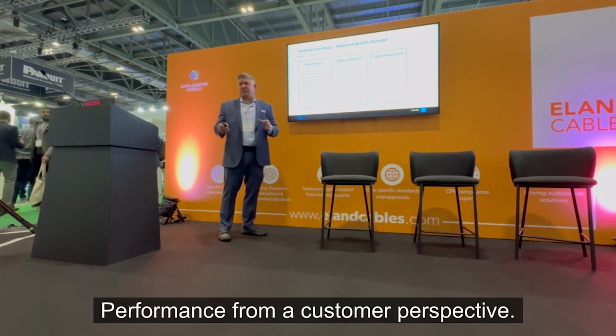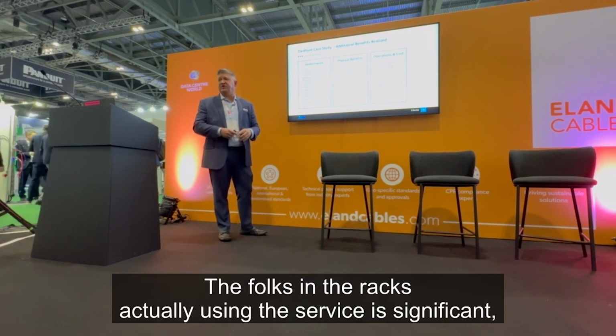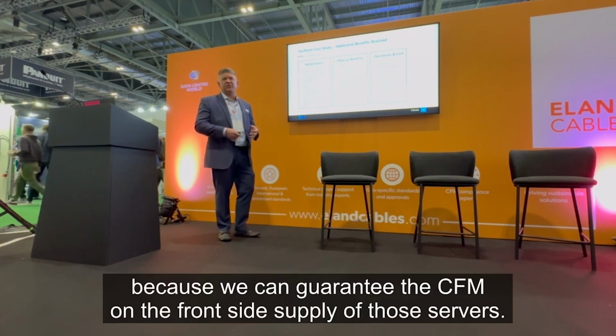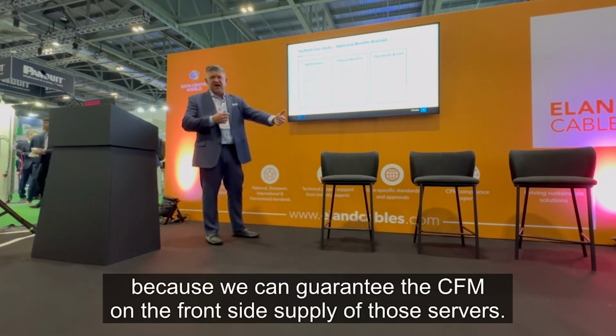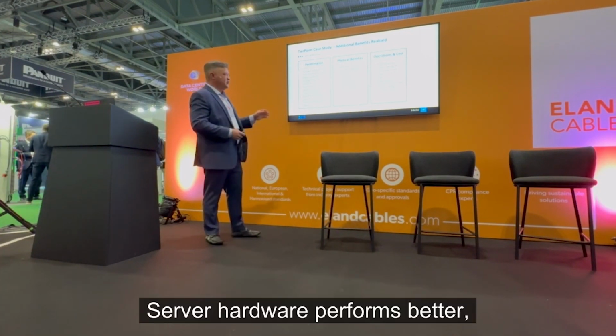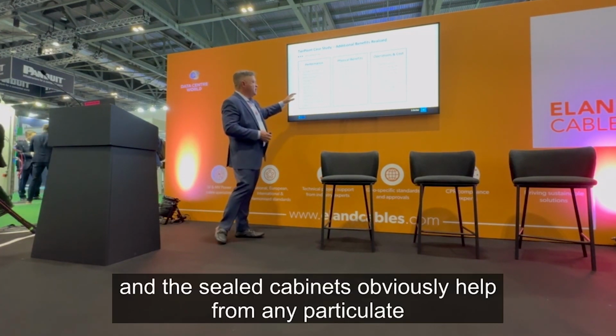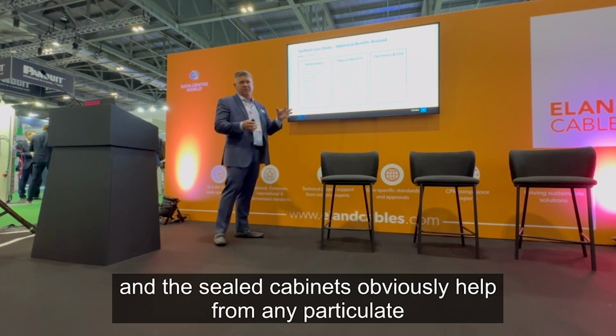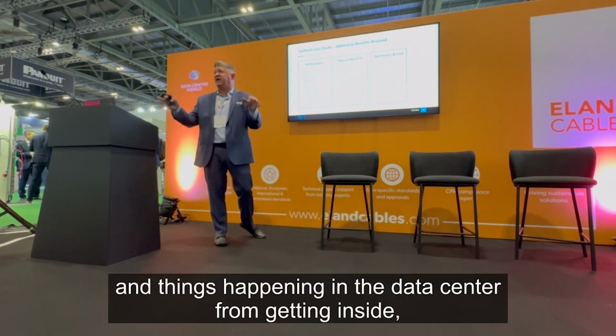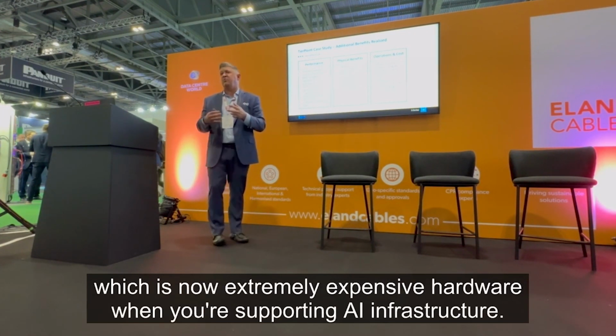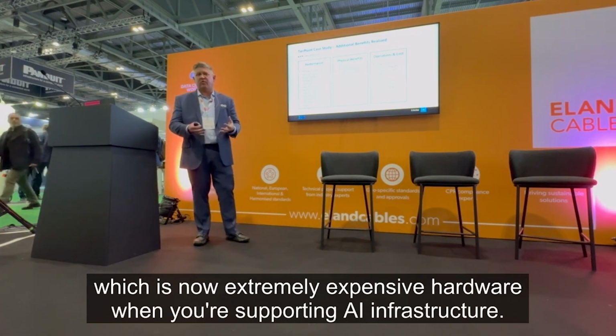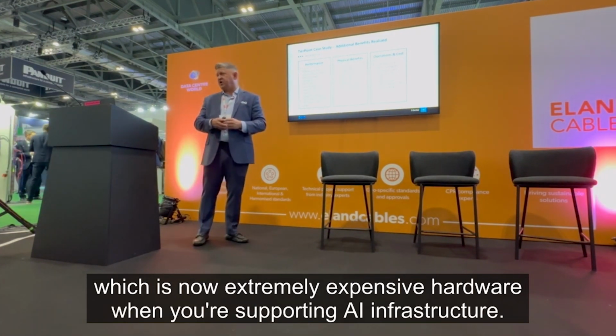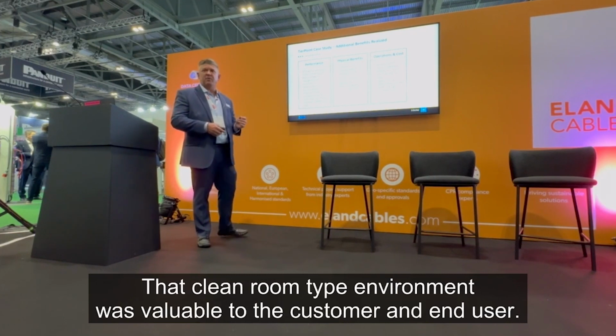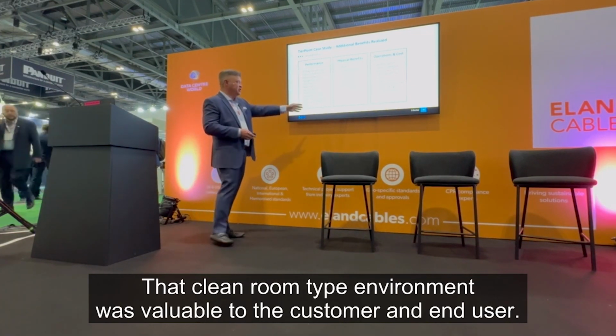Performance from a customer perspective, the folks in the racks actually using the service, is significant. Because we can guarantee the CFM at the front side supply of those servers, server hardware performs better, and the sealed cabinets help from any particulate from things happening in the data center from getting inside, which is now extremely expensive hardware when you're supporting AI infrastructure. So that clean room type environment was valuable to the customer and end user.